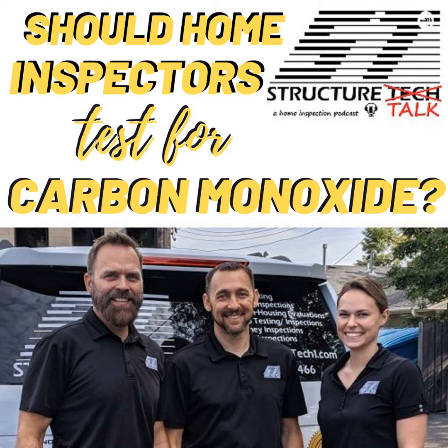Rewind, if there is a quote unquote correct time, but you want to make sure you don't do a CO test like 2 minutes after you turn on a furnace. That's too soon and you won't have an accurate reading. And Reuben, you can probably quote code on what that says. I can't, but I just know that you need to let that furnace get to what we call steady state before you do that combustion gas test on it.